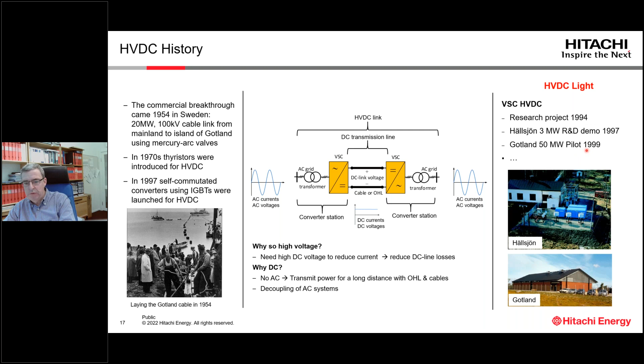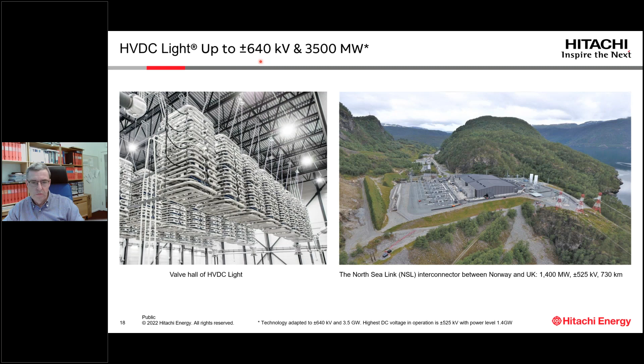And now you could see where we are today. Today we could deliver HVDC Light, HVDC links up to 640 kilovolt and with a power rating of 3.5 gigawatts. To the left here you could see a photo of how the converter looked like inside the house. What we call in HVDC language, the converter is called valve, and the house is called valve hall. To the right here, you could see how a site looks like. This site here is in Norway for the North Sea Link interconnector between Norway and UK.